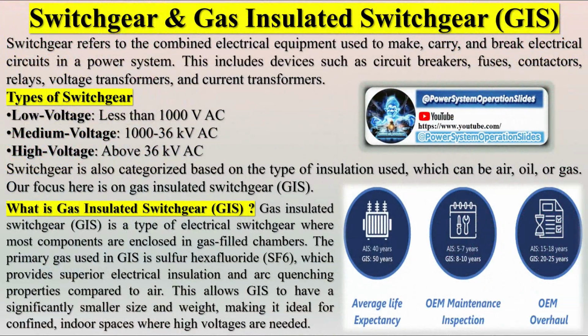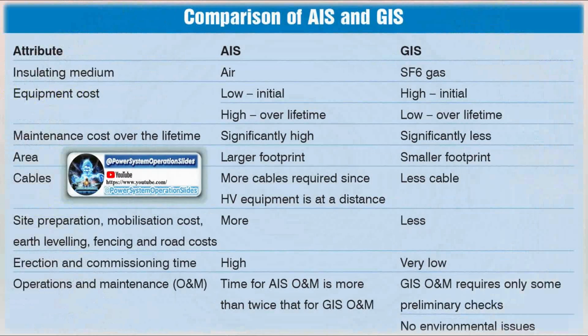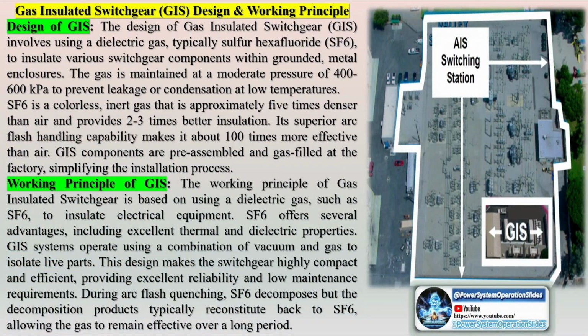Switchgear refers to the combined electrical equipment used to make, carry, and break electrical circuits in a power system. This includes devices such as circuit breakers, fuses, contactors, relays, voltage transformers, and current transformers. Types of switchgear: low voltage, less than 1000 VAC; medium voltage, 1 to 36 kVAC; high voltage, above 36 kVAC. Switchgear is also categorized based on the type of insulation used, which can be air, oil, or gas.